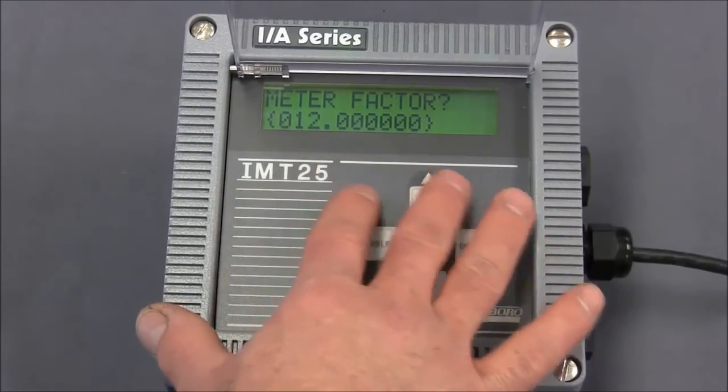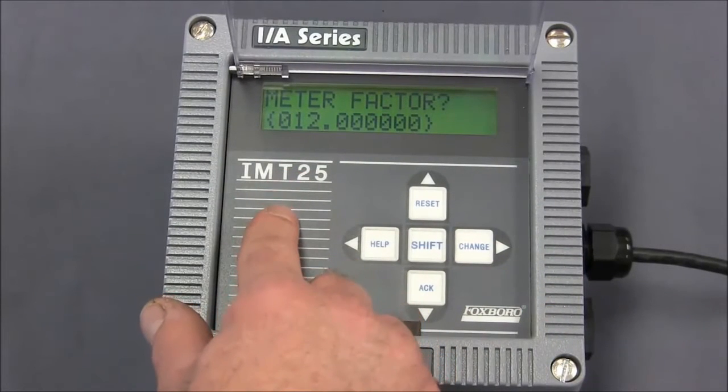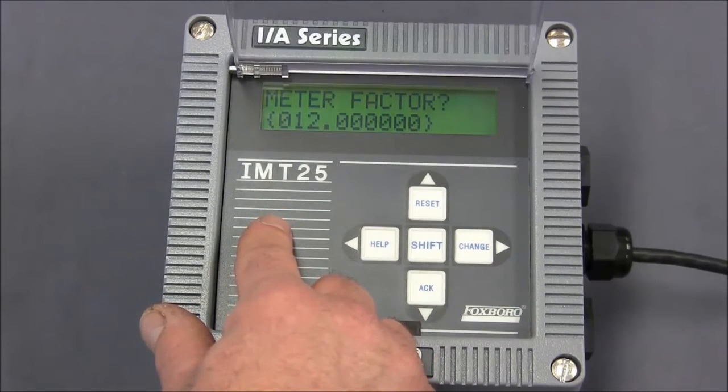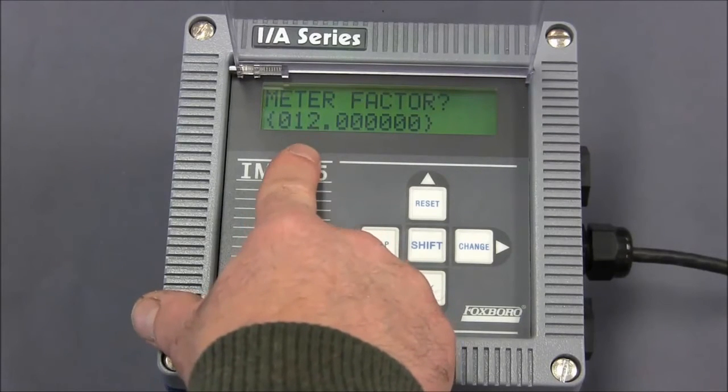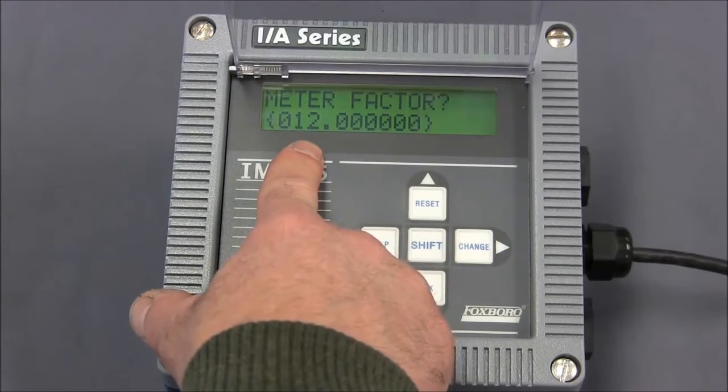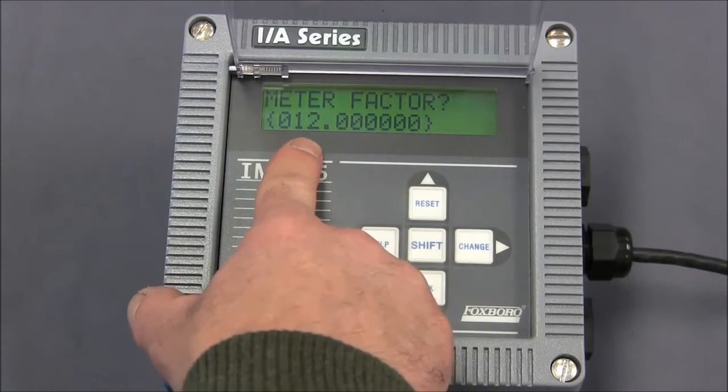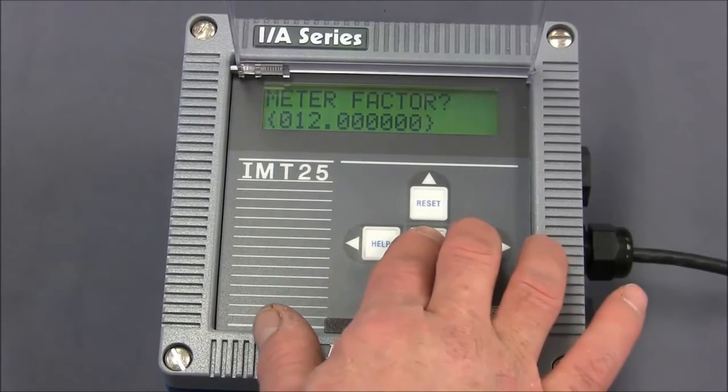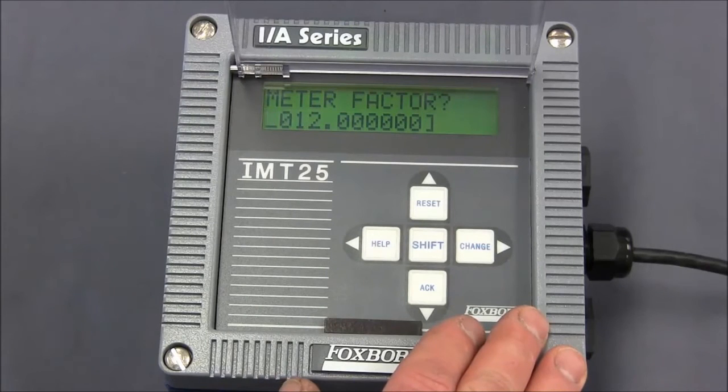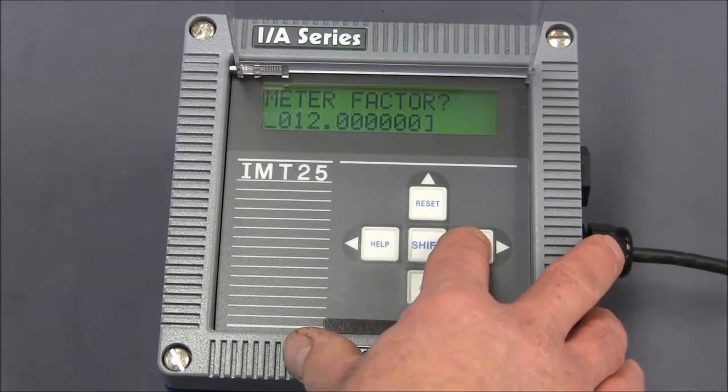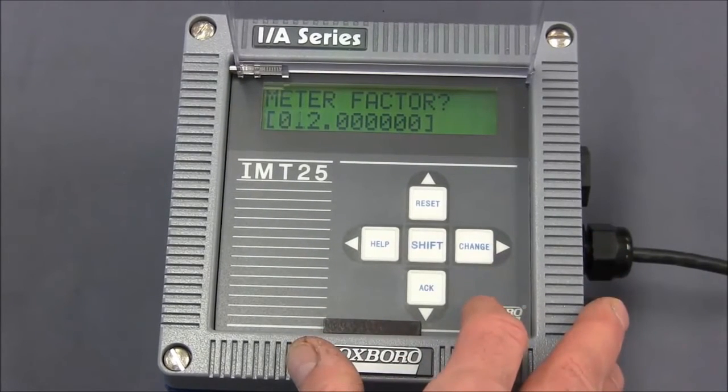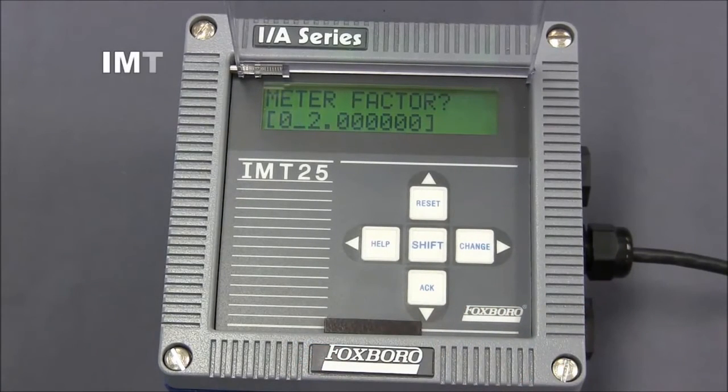Now, this is the meter factor that's currently entered into the transmitter. The default is 12, which represents the average calibration factor for a two-inch flow tube. To change this meter factor number from 12 to the meter factor that's stamped on your flow tube, you would simply do the shift and change keys together to get the transmitter into edit mode.